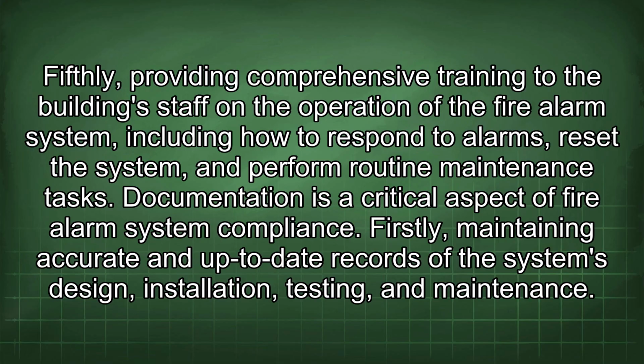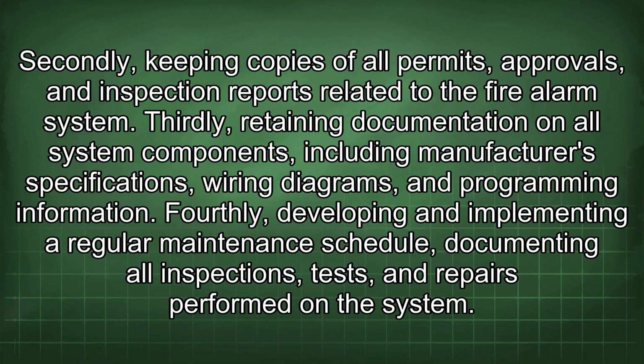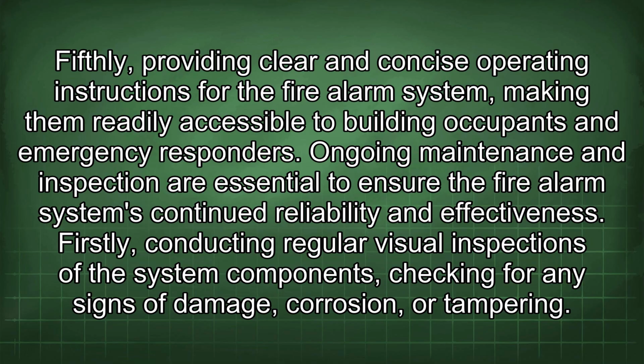Documentation is a critical aspect of fire alarm system compliance. Firstly, maintaining accurate and up-to-date records of the system's design, installation, testing, and maintenance. Secondly, keeping copies of all permits, approvals, and inspection reports related to the fire alarm system. Thirdly, retaining documentation on all system components, including manufacturer specifications, wiring diagrams, and programming information. Fourthly, developing and implementing a regular maintenance schedule, documenting all inspections, tests, and repairs performed on the system. Fifthly, providing clear and concise operating instructions for the fire alarm system, making them readily accessible to building occupants and emergency responders.